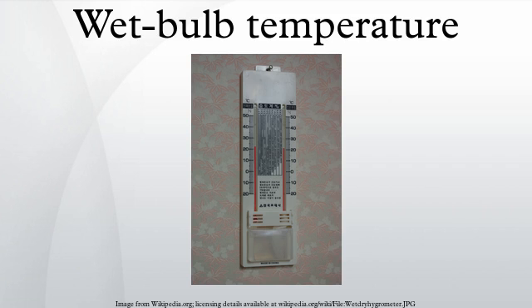Wet bulb temperature is largely determined by both actual air temperature and the amount of moisture in the air. The thermodynamic wet bulb temperature is the minimum temperature which may be achieved by purely evaporative cooling of a water-wetted, ventilated surface. For a given parcel of air at a known pressure and dry bulb temperature, the thermodynamic wet bulb temperature corresponds to unique values of relative humidity, dew point temperature, and other properties. The relationships between these values are illustrated in a psychrometric chart.